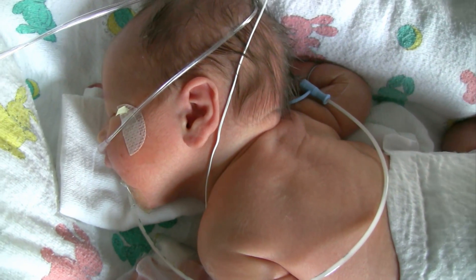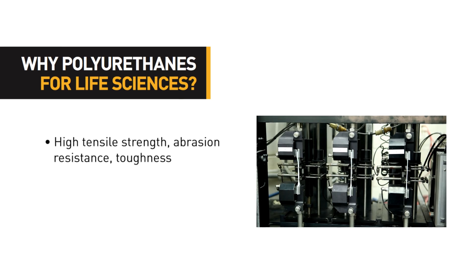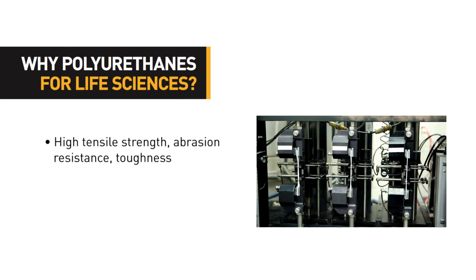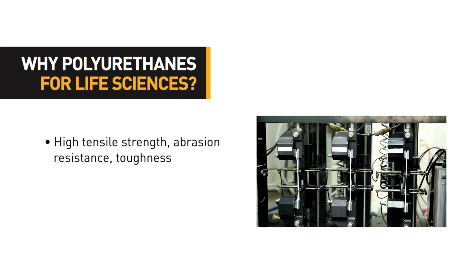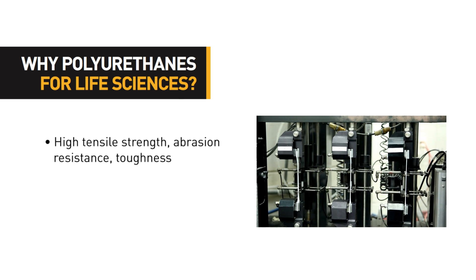The use of polyurethane materials in medical devices has been increasing over the years due to their many desirable characteristics, such as availability in a wide range of durometers spanning the range from approximately 20 Shore A to 80 Shore D, and excellent mechanical properties including high tensile strengths and some of the best abrasion resistance of any polymer.